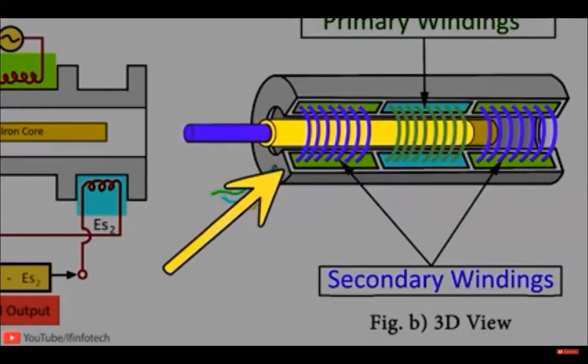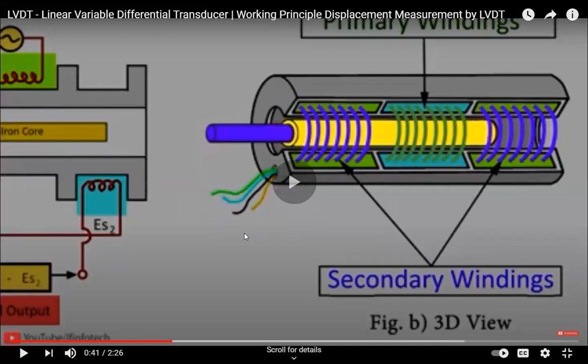Inside the insulating cylinder, a magnetic core is placed, which is free to move. As you can see, the yellow core is moving to and fro. As displacement takes place, this yellow cylinder moves inward and outward. If this core is at the secondary 1 position, secondary 1 voltage will be more. If the core is at this position here, then secondary 2 voltage will be greater. So in this way it works.